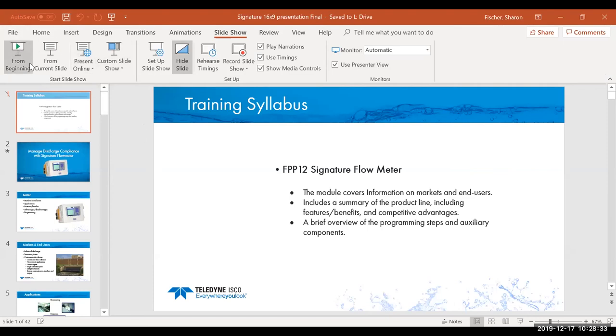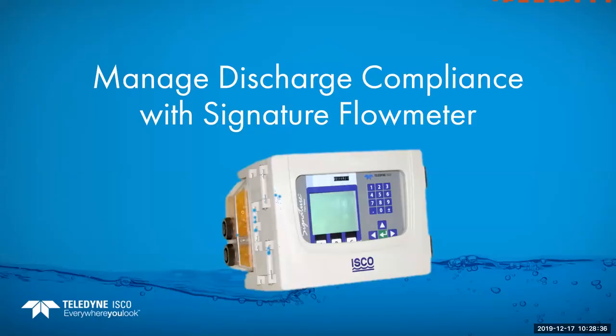Can the pH probe for a 201 pH module be used instead of the 301 module? The 301 module is required for the Signature. It just talks completely differently to the Signature versus the old 4200. So you would need to get the 301 pH module, but you can use the exact same pH sensor. The sensor with the 4-pin connection that goes on the 201 module, you could use that exact same sensor with the 301. Maybe I misunderstood that, but yes, you could use the same pH probe for both of those.